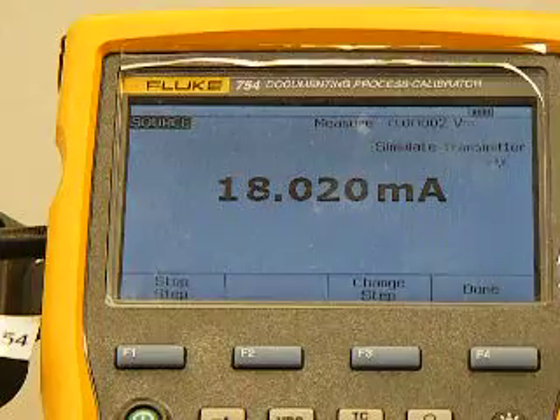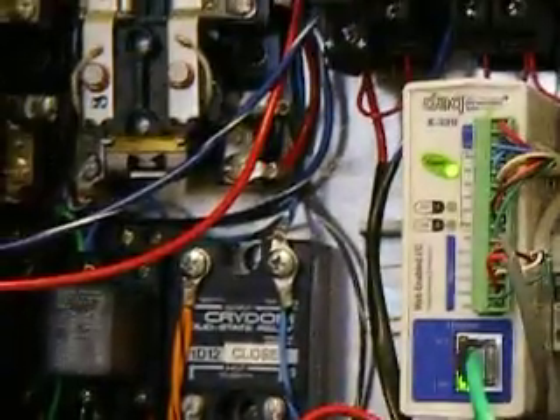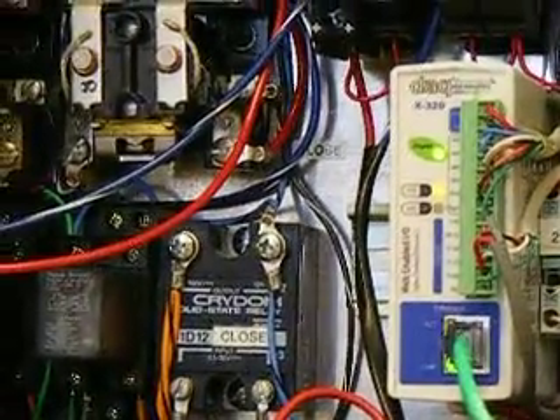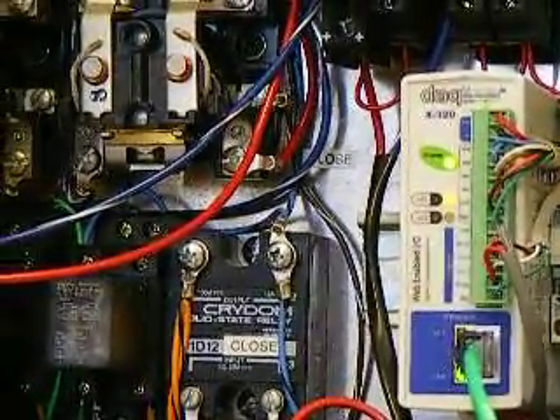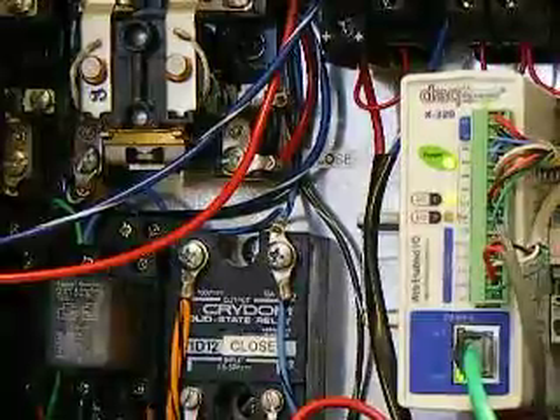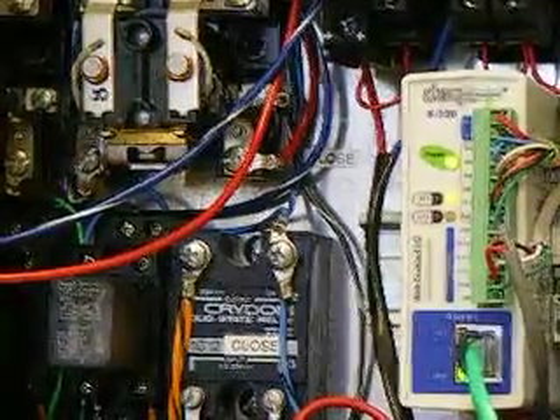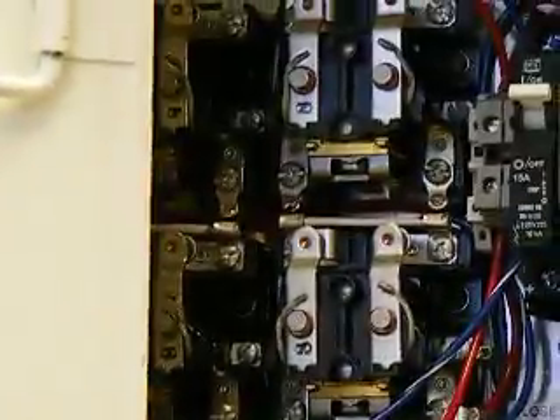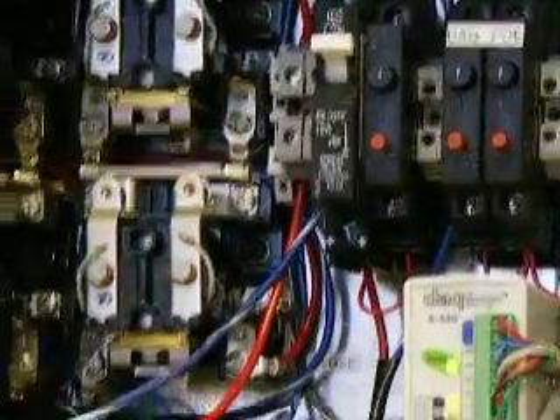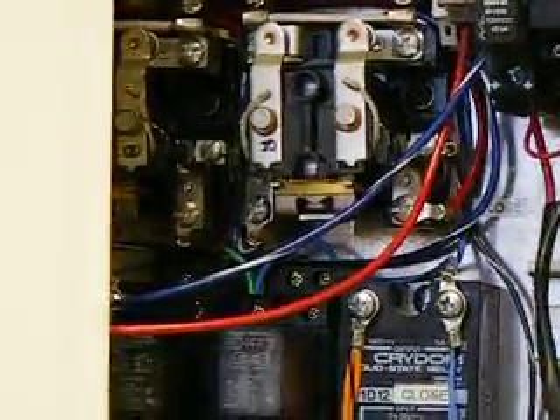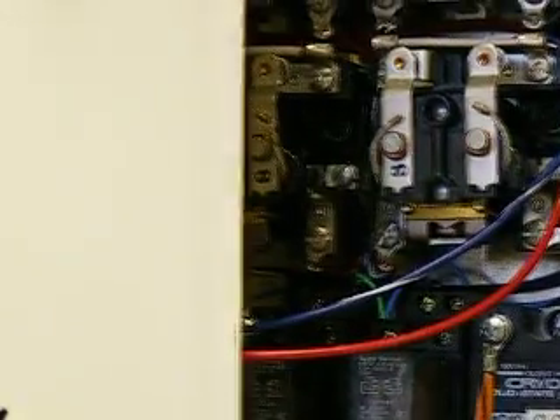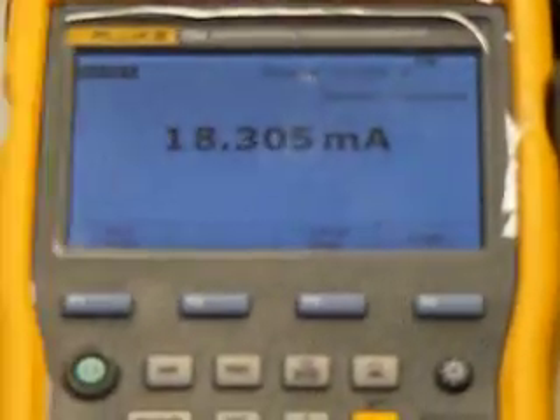milliamps, we should hear the relays in the panel kick. You'll see the I/O light will come on there for channel 1. That would be at that point opening the valve because we would have high pressure. That activates the relays here. The output is the blue and red wire you see running across there, which are not permanent at this point. The valve position actually will be managed by this transmitter.